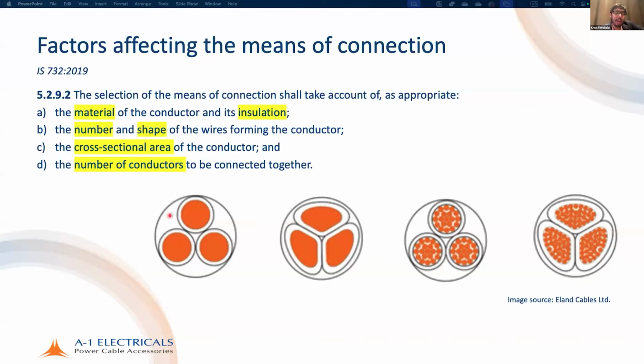You can see this is a multi-core, three-core cable with class 1 conductors. This is a three-core cable with class 1 shaped conductors. This is a three-core cable with class 2 conductors. This is a three-core cable with class 2 shaped conductors. All of these factors affect how we can connect and what product we have to use to connect.